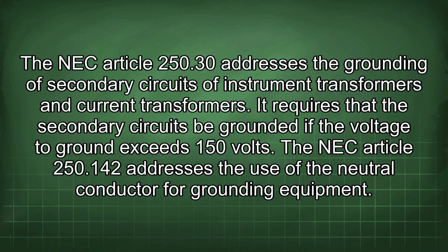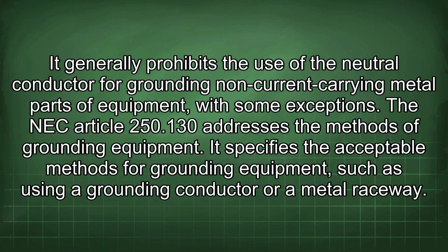The NEC Article 250.30 addresses the grounding of secondary circuits of instrument transformers and current transformers. It requires that the secondary circuits be grounded if the voltage to ground exceeds 150 volts. The NEC Article 250.142 addresses the use of the neutral conductor for grounding equipment. It generally prohibits the use of the neutral conductor for grounding non-current carrying metal parts of equipment, with some exceptions.